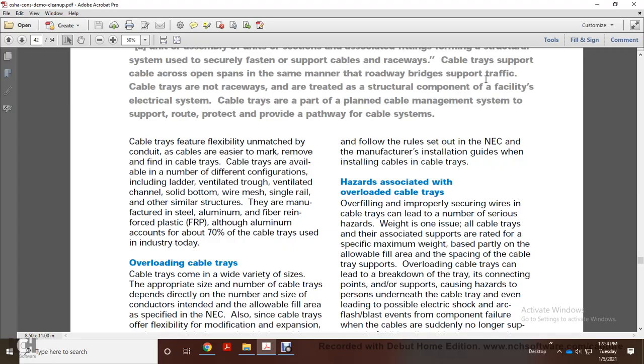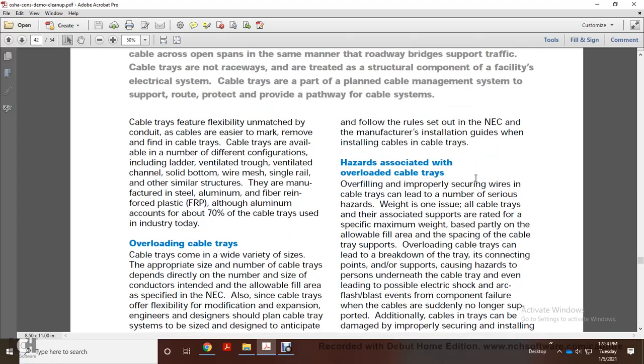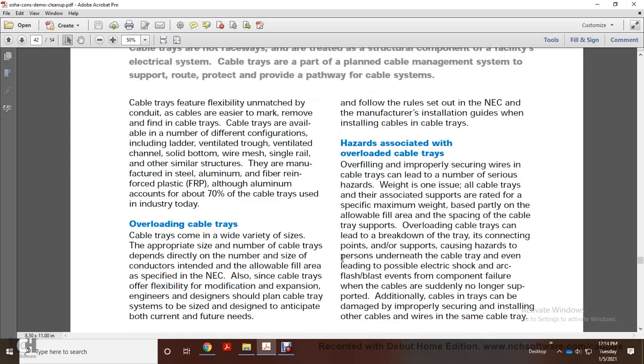Alright, hazards associated with overloaded cable trays. Overloading and improperly securing wire in the cable tray, issues with the associated supports, exceeding the maximum allowable fill area, and poor spacing of the cable and tray supports can all lead to overloaded cable trays. This can cause a breakdown of the tray at the connection points of the supports, causing harm to personnel underneath the cable tray, even leading to possible electrical shock, arc flash, and blast events from component failure when the cable is suddenly no longer supported.